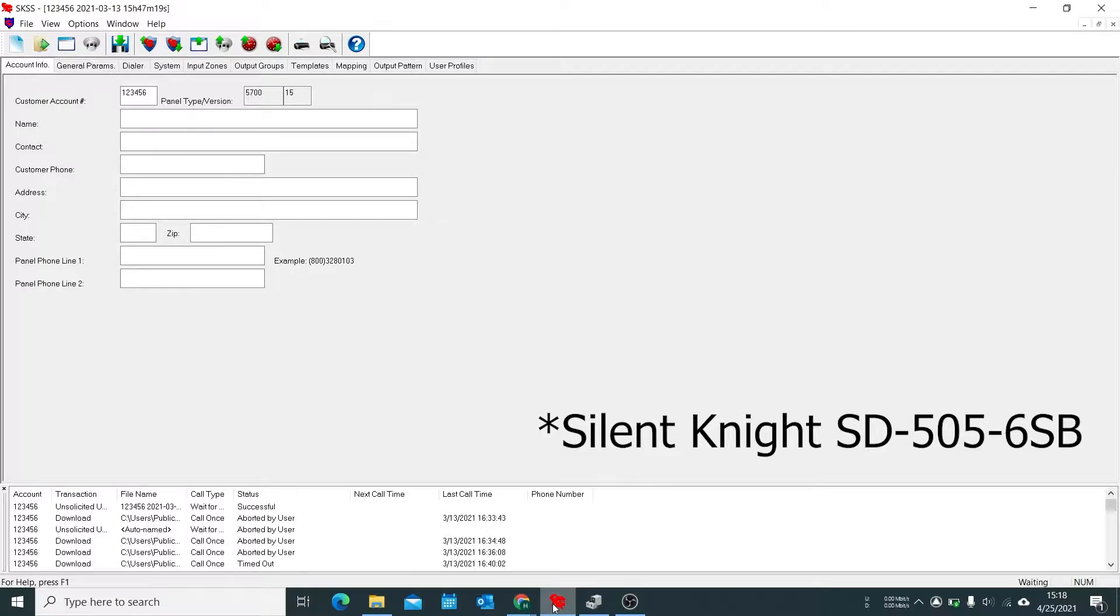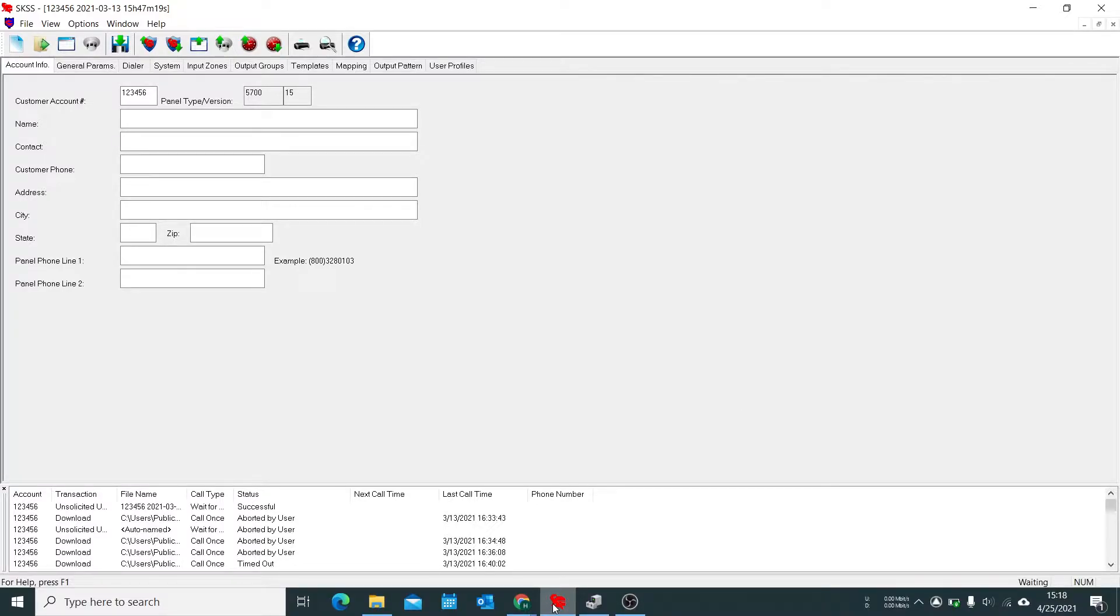The way that Silent Knight sounder bases work is that they are tied to a specific point on your SLC loop. This is done by basically sniffing for data going both inbound and outbound of a detector which is connected in parallel to the sounder base card itself.